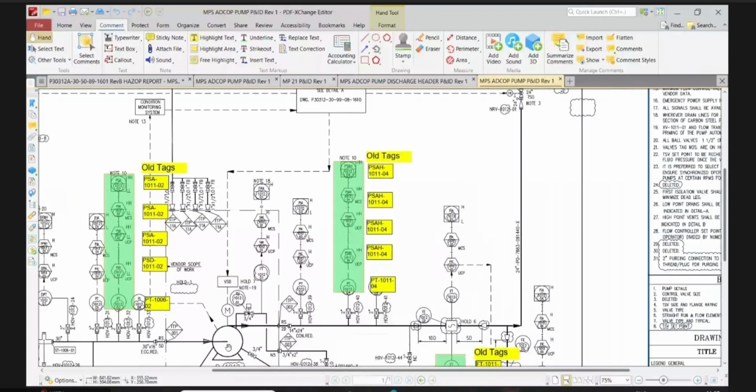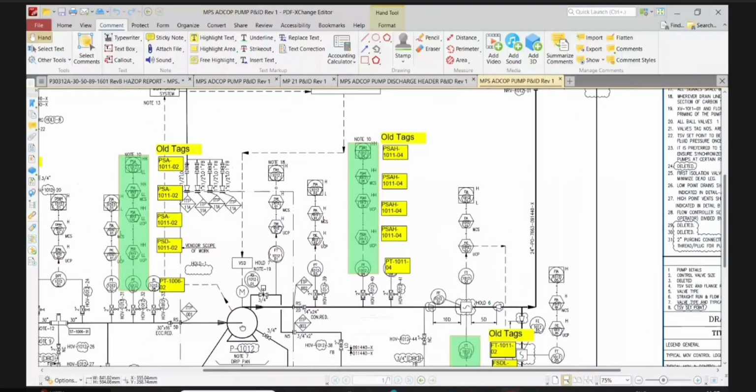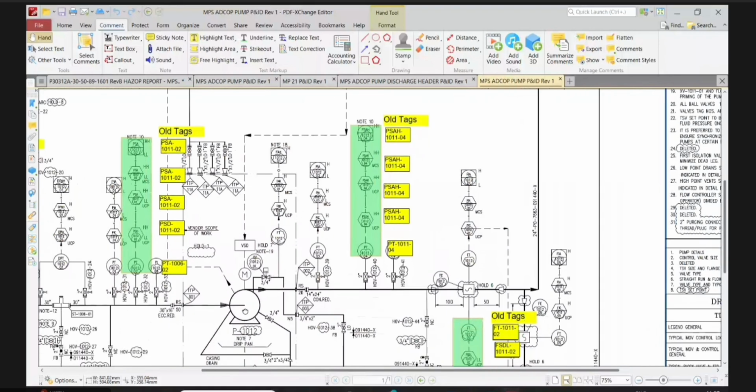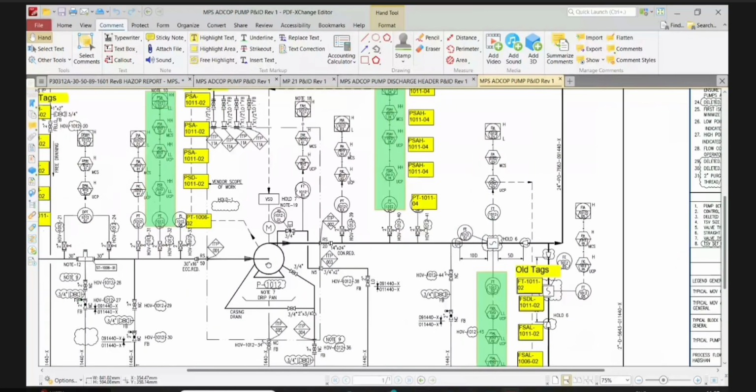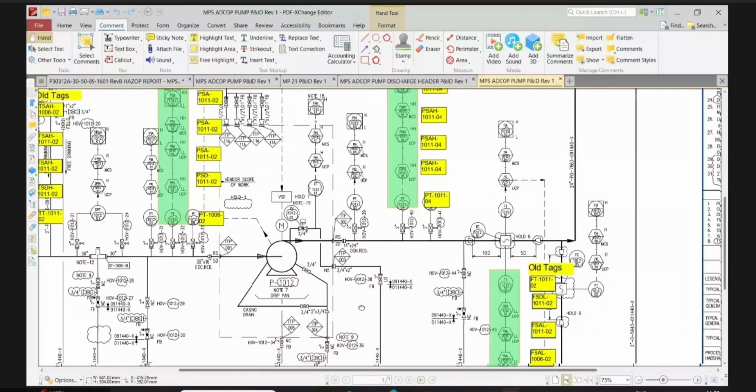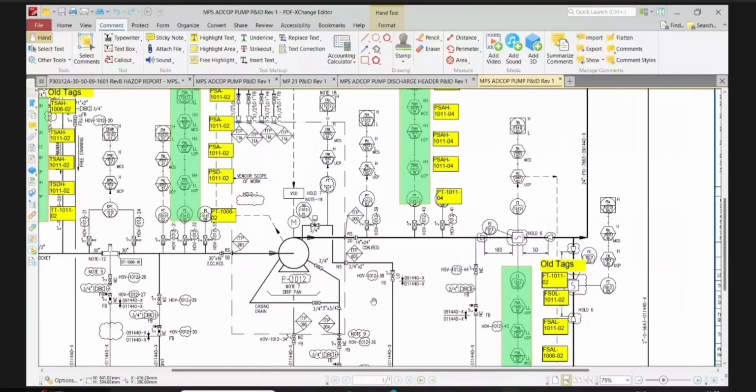Okay. For the pump itself, as the casing of the pump or the mechanical seal cartridge, the seal chamber pressure is equal to the maximum suction pressure plus delta P divided by number of stages, here 4 stages, and multiplied by 15%. This is the seal chamber pressure.